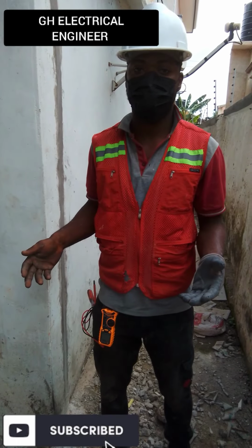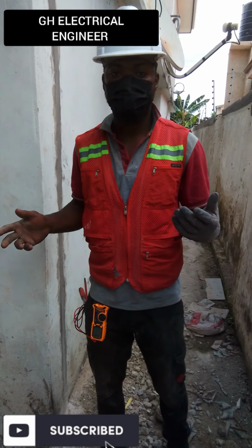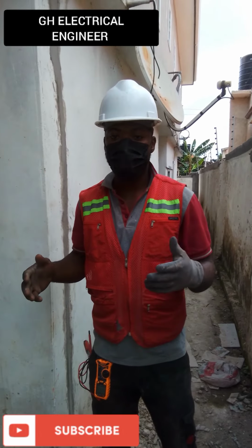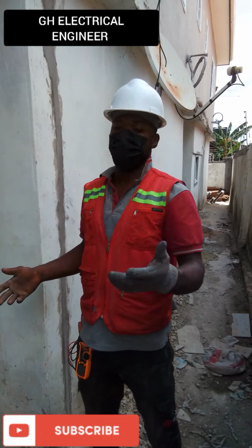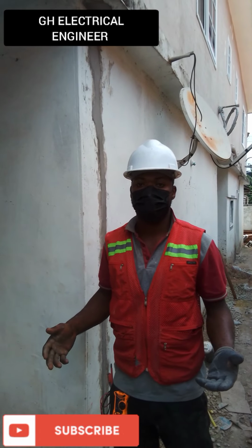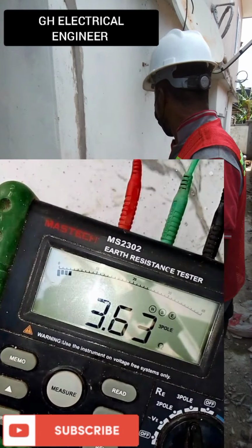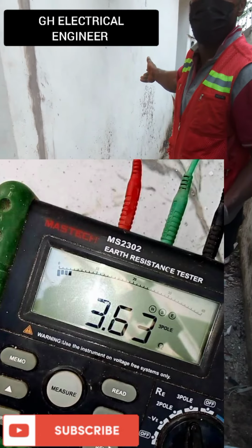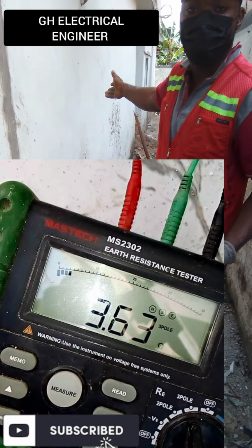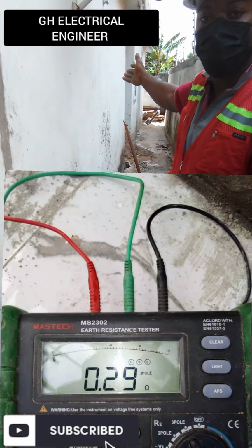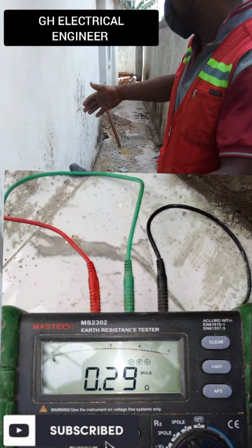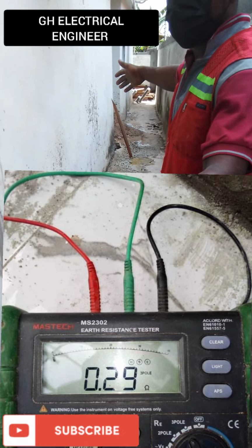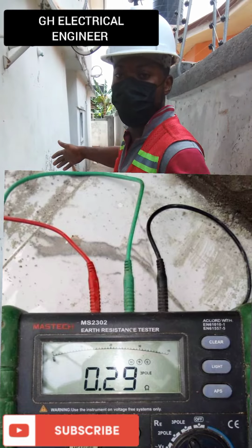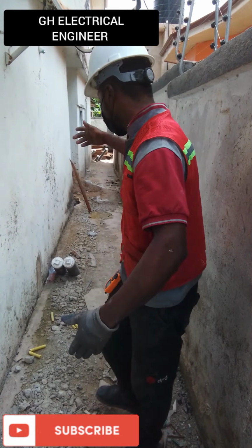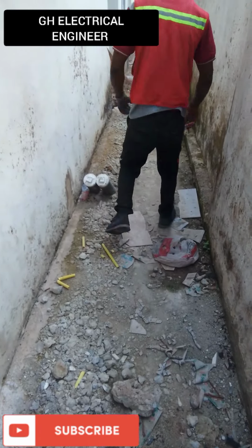And we decided to go another 10 meters away to bury another earth rod, with 16 millimeter square cable, and we got almost 3.63 ohms. And then we added another 16 millimeter square cable to it, and we got 0.29 ohms, which is really good. The final installation, I was so happy. So, guys, from here, let's go and check another earth rod.